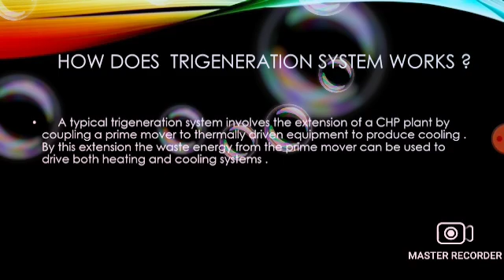Generators lose heat as they create electricity. A trigeneration facility captures this heat that would otherwise be lost and uses it to generate both hot and cold water. The chilled water is created by an absorption chiller, which is driven by the excess heat and operates like a refrigerator, creating water at a sufficiently low temperature to be used for air conditioning.